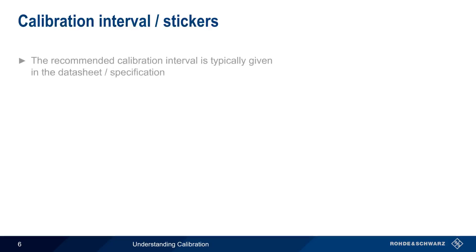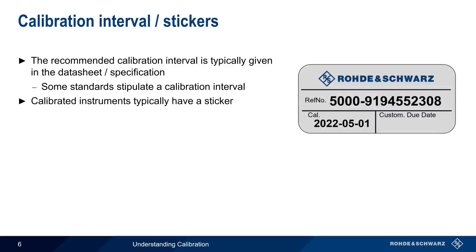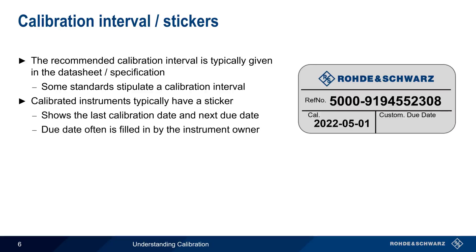Instrument calibration is done on a regular or periodic basis, and the recommended calibration interval is typically given in the instrument data sheet or specification, although in some cases various technical standards may stipulate a certain calibration interval. Stickers are often placed on instruments during calibration, showing both the last calibration date as well as the next date when calibration is due, although the calibration due date is usually filled in by the instrument owner, not the calibration lab.